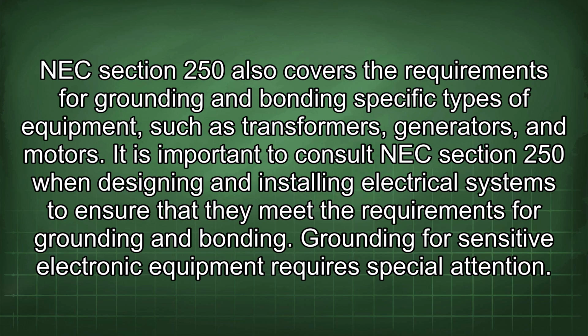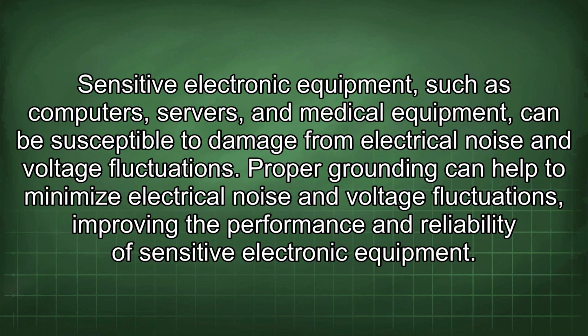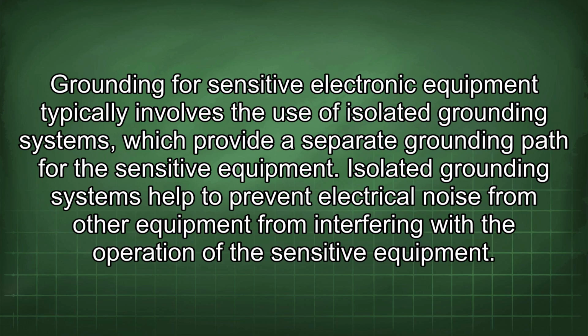Grounding for sensitive electronic equipment requires special attention. Sensitive electronic equipment, such as computers, servers, and medical equipment, can be susceptible to damage from electrical noise and voltage fluctuations. Proper grounding can help to minimize electrical noise and voltage fluctuations, improving the performance and reliability of sensitive electronic equipment. Grounding for sensitive electronic equipment typically involves the use of isolated grounding systems, which provide a separate grounding path for the sensitive equipment. Isolated grounding systems help to prevent electrical noise from other equipment from interfering with the operation of the sensitive equipment.